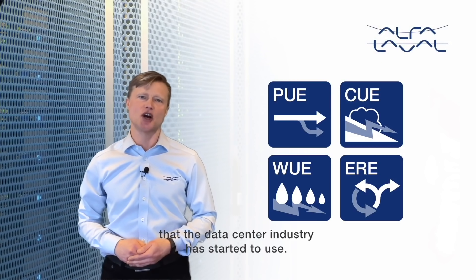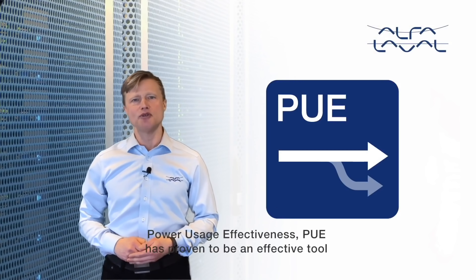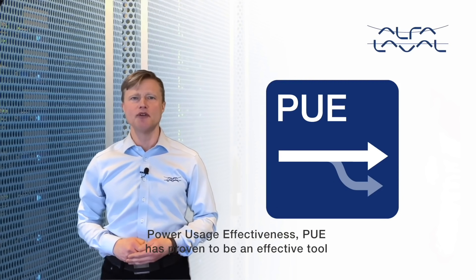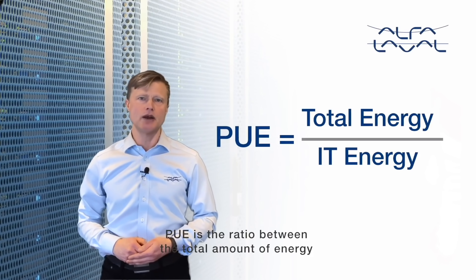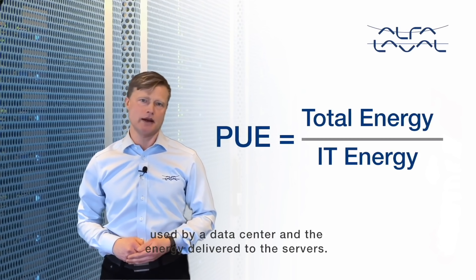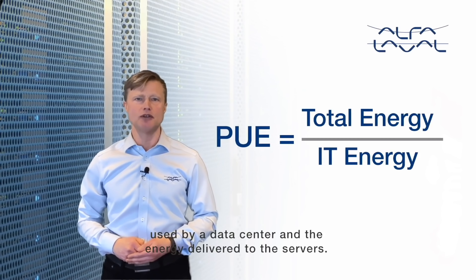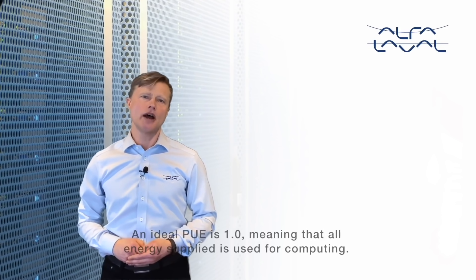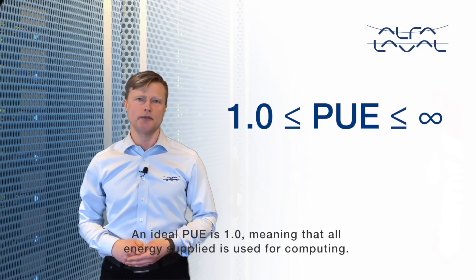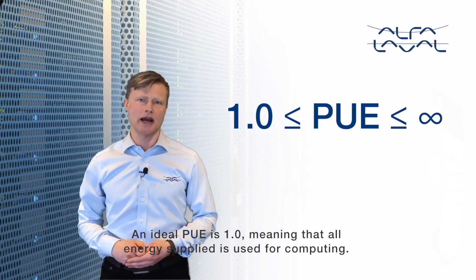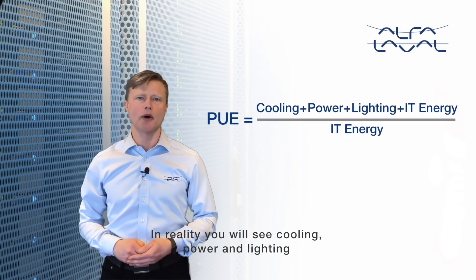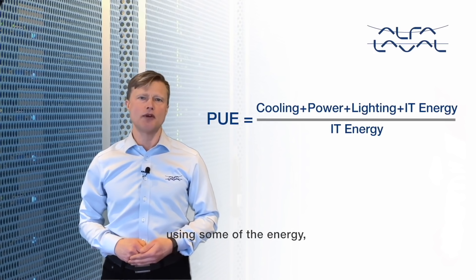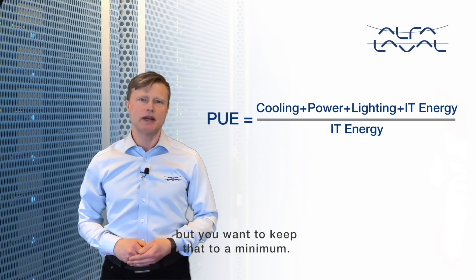Power Usage Effectiveness (PUE) has proven to be an effective tool for measuring data center energy efficiency. PUE is the ratio between the total amount of energy used by a data center and the energy delivered to the servers. An ideal PUE is 1.0, meaning that all energy supplied is used for computing. In reality, cooling, power, and lighting use some of the energy, but you want to keep that to a minimum.